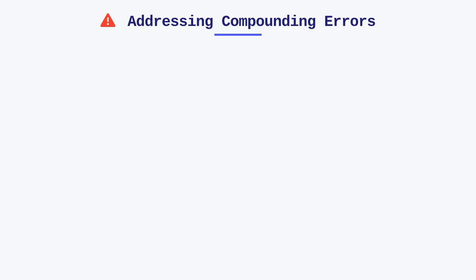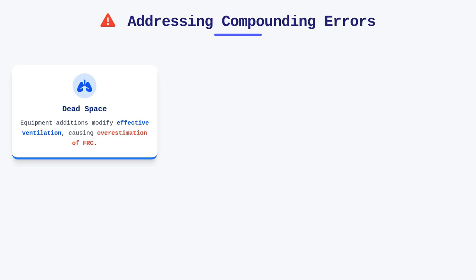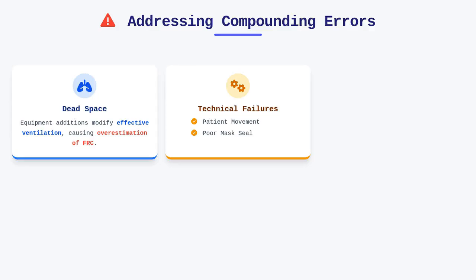Finally, we must address the compounding errors that can invalidate our findings across all these modalities, starting with dead space. Any equipment that adds dead space to the breathing circuit will modify the effective ventilation and, if not precisely corrected in our software, will lead to an overestimation of the functional residual capacity. We also see technical errors stemming from patient movement, poor mask seal, or improper temperature stabilization of the gas sensors.